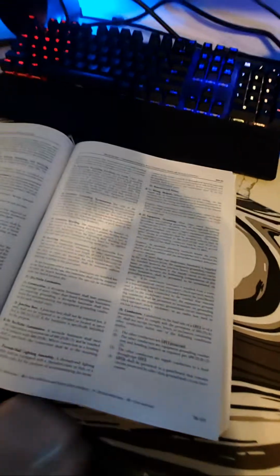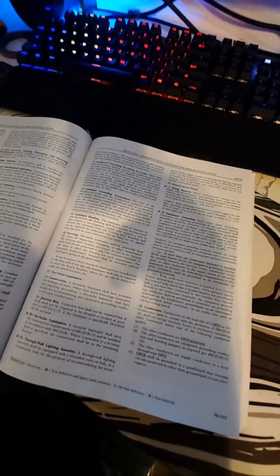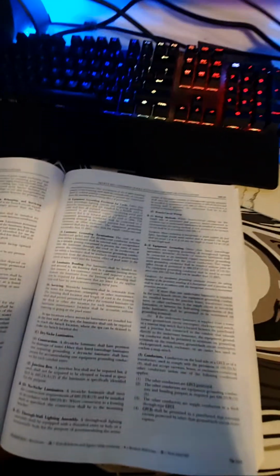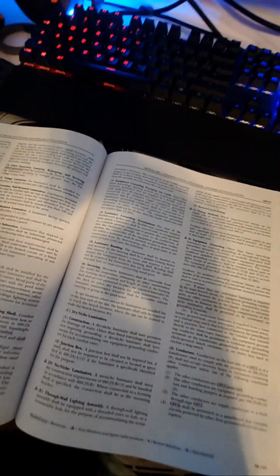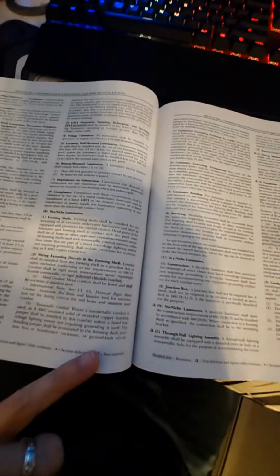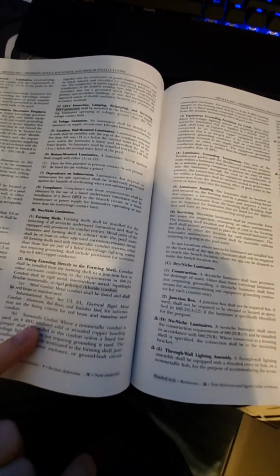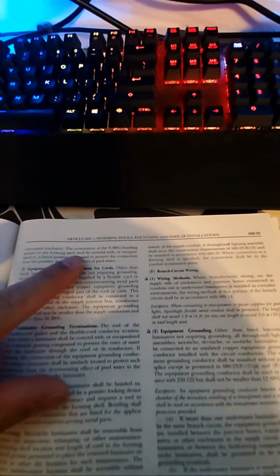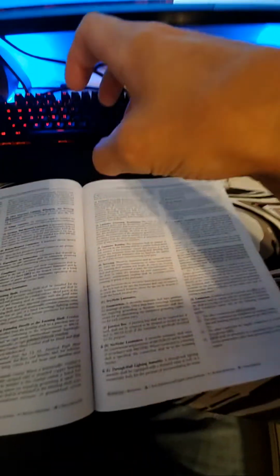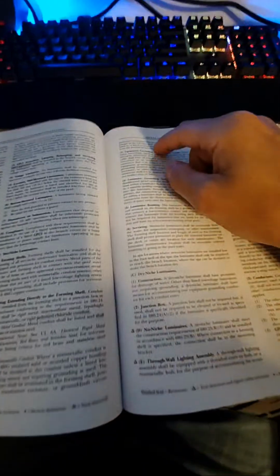And the requirement for that, you've actually got to put a listed potting compound over the lug once you're inside the light. So let's see if we can find that. There's the non-metallic conduit there, right? And it's going to continue to say, shall be covered or encapsulated with a listed potting compound to protect the connection from the possible deteriorating effects of the pool water. So like I said before, the code is going to be right about here. And I'm glad to see that they didn't move it too far away from where I knew it was.